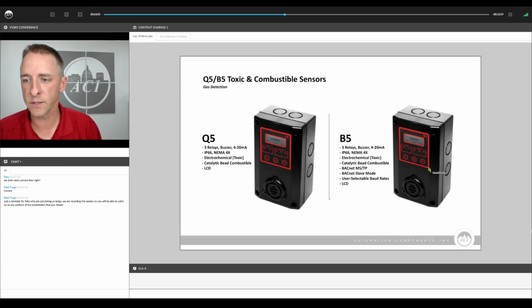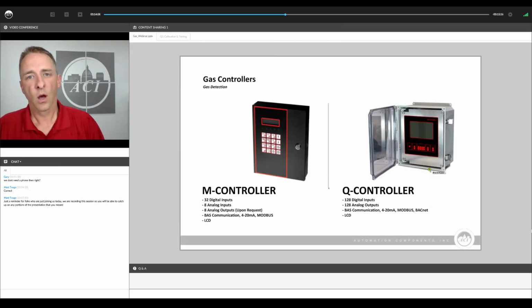We've seen a lot of requirements recently for standalone gas sensing systems that operate independently of your BMS system. So in those cases, we can provide one of two different small control panels that operate directly with our gas sensors. The M controller is a small compact panel that can accept up to 32 digital inputs or 8 analog inputs and 8 analog outputs. And the Q controller over on the right-hand side of the screen can take up to 128 digital and 128 analog inputs. And both are easily configurable and programmable.